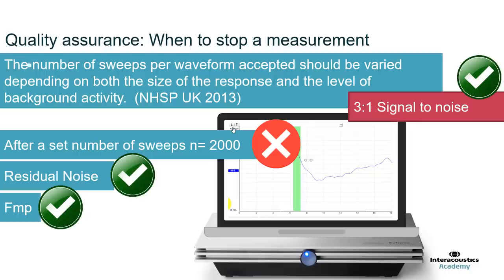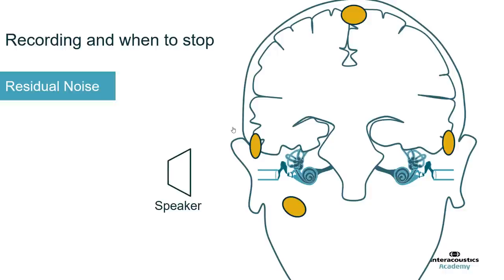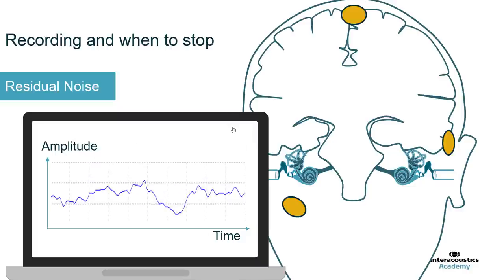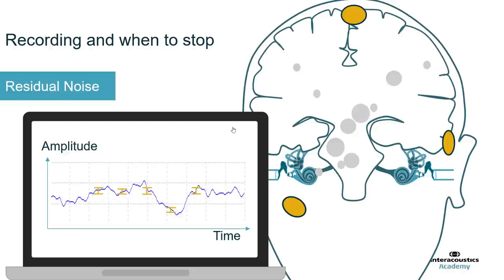The Eclipse has some really nice technologies to help: residual noise and FMP. Rather than using traditional methods like running 2000 sweeps, we should rely on more accurate estimations such as the residual noise algorithm, FMP, or the UK NHSP signal-to-noise technique. The residual noise calculator measures the variance across five points on the waveform. At the beginning of the test, variance is very high due to high residual noise. As testing continues and noise reduces, variance reduces. When variance is at a low level, we can estimate there is a small amount of noise in the recording and stop testing. In infants, we use a value of 25 nanovolts.